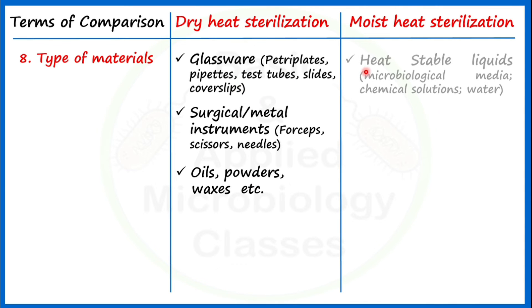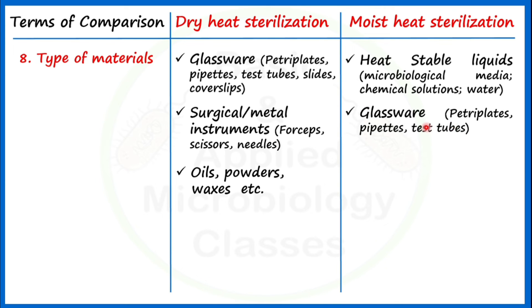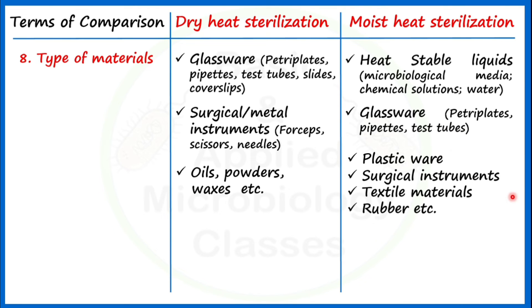For moist heat sterilization, heat-stable liquids can be sterilized — the liquid must be heat stable since moist heat has very high penetration power. Microbiological media, whether broth or agar, liquid or solid, are always sterilized by moist heat in the laboratory. Chemical solutions, vaccines, and water are also sterilized this way. Glassware, plasticware, surgical instruments, textile materials, and rubber can also be sterilized by moist heat sterilization.